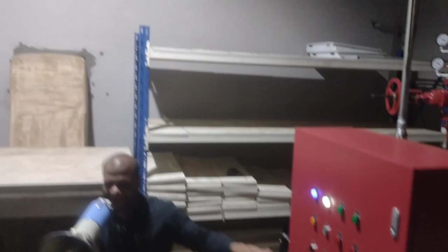If the fire is still huge, then the water will be brought to the area, but the pressure will keep dropping. When it goes down to 3.5 bar, the electric pump will start automatically. So the water will move through the same network to that area to put off the fire. The jockey and electric pumps will run in parallel to put off the fire. This is the fire scenario.